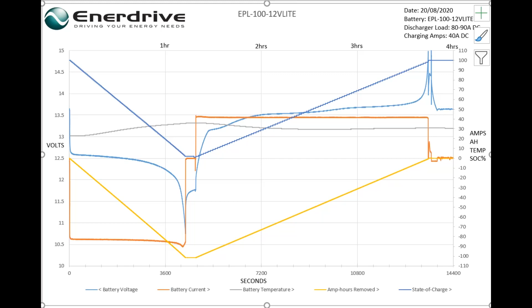We sort of go beyond what you would normally do in a typical setup or typical load. Normally you would have your fridges, your loads, lights cycling on and off, but we want to show what the batteries and the cells can do, and also prove that even running those bigger loads you'll still get the full 100 amps out of our battery.